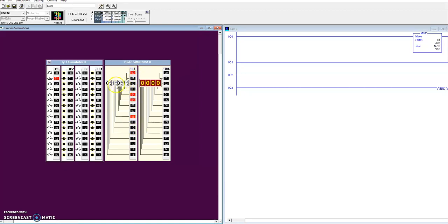Because the way that this thing is connected, this basically looks at this as these first 4 digits here represent a 1. This next group of 4 digits represent a 3. This next group represent a 1. And this last group of 4 bits here represent a 0. So we're basically using a 16-bit register broken up into 4 groups of 4 to represent these 4 numbers. But our PLC sees this as one 16-bit number, which it calls 305. So that's no good to us.